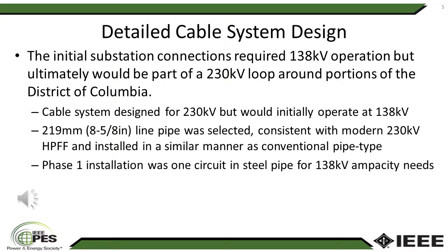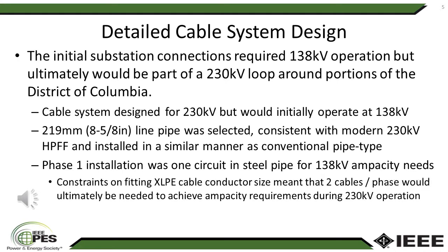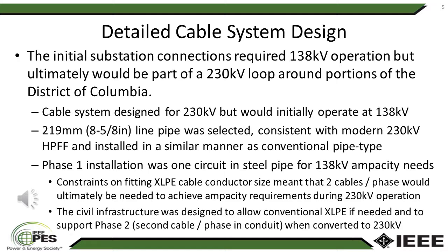Phase 1 of the project, operating at 138 kV, utilized 1 circuit in steel pipe to meet the ampacity needs. However, constraints on fitting XLPE cable into the steel pipe would mean that 2 cables per phase would be needed to meet the ampacity goals for 230 kV operation. The civil infrastructure used on the system allowed for conventional XLPE cable if needed, and also supported the later installation of the second phase of the project.